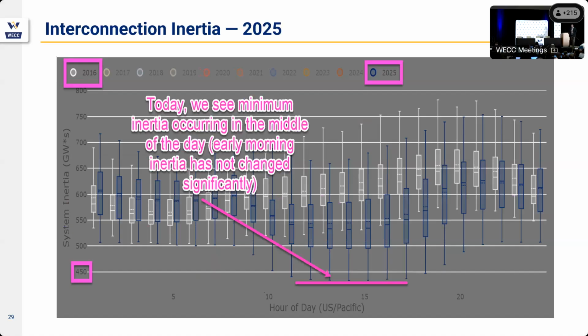So the question is what's the reliability risk to this reduction of inertia, I guess is what your real question is. We don't think it's real. We don't believe from the studies that we've done at WECC that we're hitting any minimum inertia levels by any means. 450 gigawatt seconds is still a lot of inertia on any power system. As a reference, I talked about Texas, they approach 100 gigawatt seconds, and they're about half our size, and they've set that as kind of their critical inertia level. So we don't believe from our studies that we're hitting a reliability risk, but we are changing rapidly. That's really the whole point of this, is the rapid change that we're seeing. We saw a rapid change from 24 to 25, really significant.